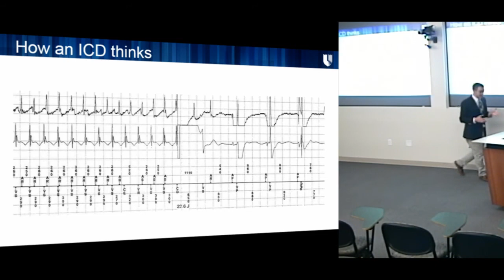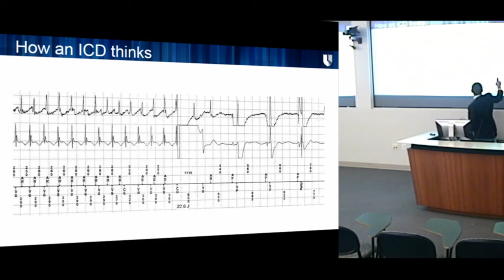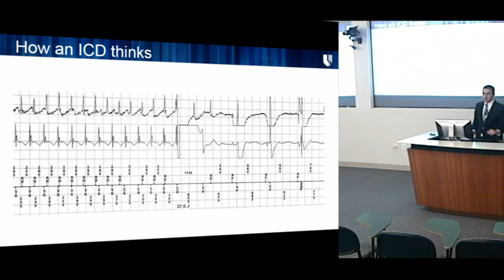Okay? And so continuously, the defibrillator monitors the heart rhythm and basically decides, is what's going on good or is it bad? And if what's going on is bad, then after a predetermined amount of time, which again you program, you can deliver either that pacing or in this situation, there's a shock, and that's what this deflection is. And then you can see that right here before the shock, there's a fast rhythm, so lots of spikes over a short period of time. And after the shock, you end up getting the rhythm reset. Okay? And just based on knowing what these different labels are, the defibrillator is now happy with the rhythm as opposed to before when it shocked the patient out.